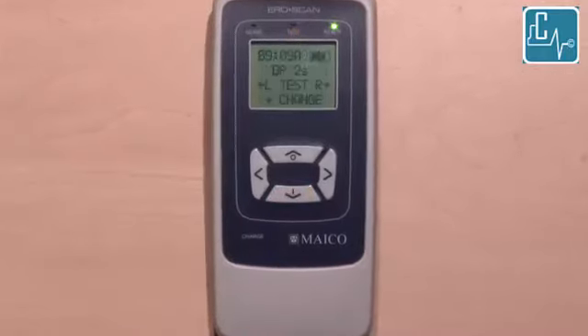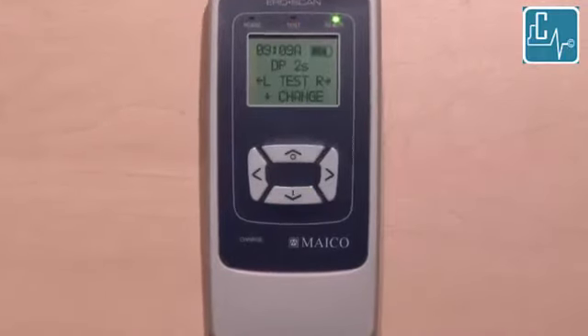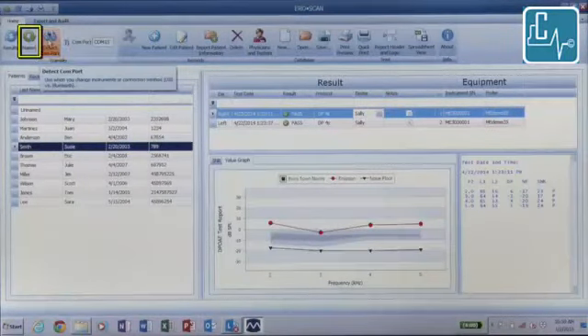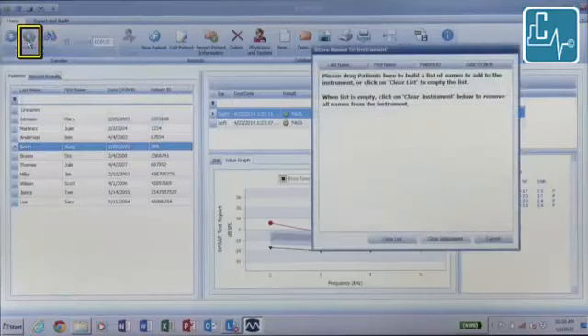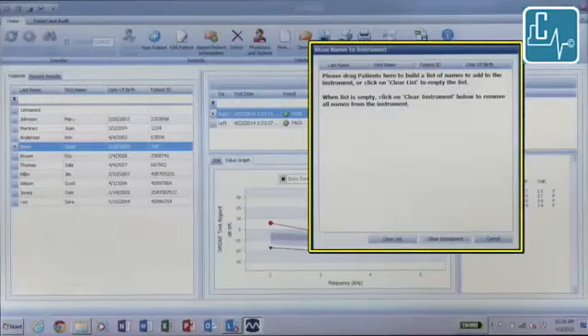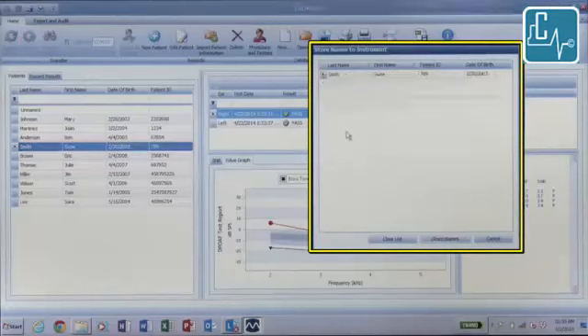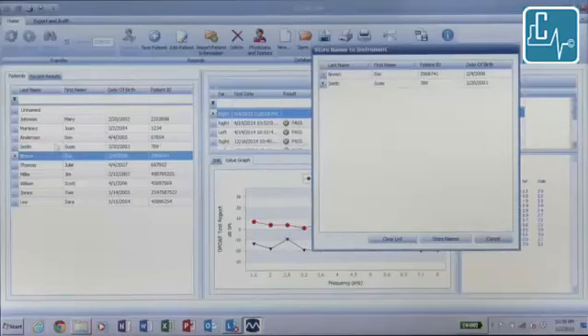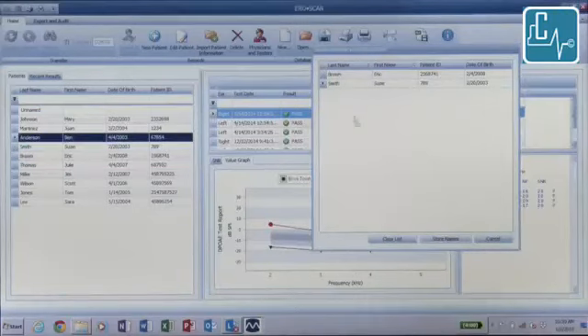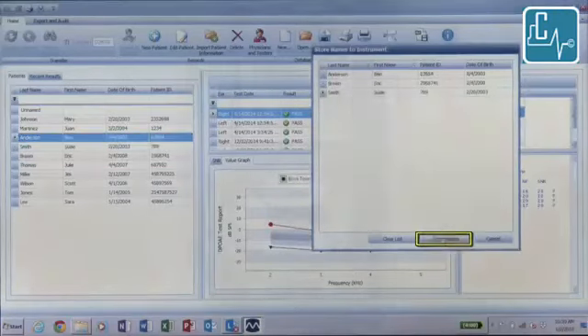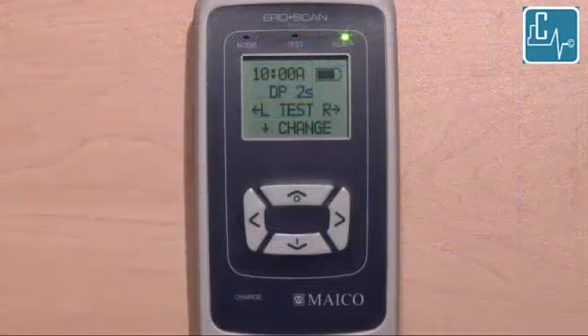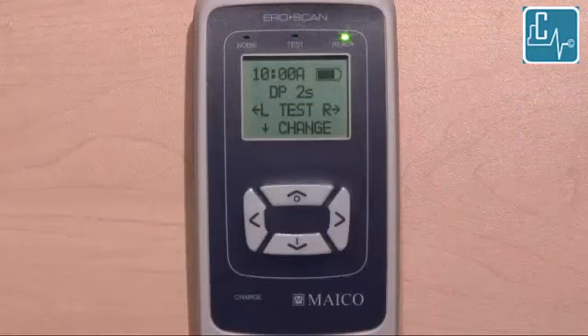Turn on the ERO SCAN device by pressing the down arrow key. If this is the first time you are plugging this device into the computer or the device is not recognized, press the Detect COM port button. Press Names to download patient names into the handheld device. A window will open. Simply drag all the names you wish to download from the database into the window. Then press Store Names. Names will now be displayed in the handheld device. Up to 50 names can be stored on the device.